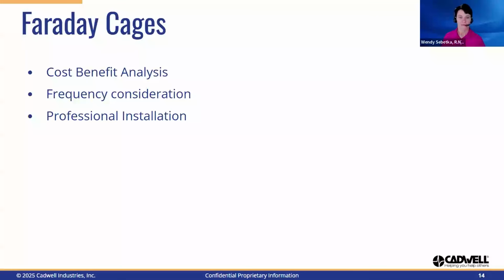The question of installing a Faraday cage always comes up when talking about preventing noise. If considering installing a Faraday cage, you will want to perform a cost-benefit analysis to ensure the expense is worth the benefit. You will want to ensure the proper cage is selected, taking into consideration the frequencies you need to block, as high frequencies require a smaller hole size, while lower frequencies would require a larger hole size. Installing the incorrect option could lead to no improvement or even worsening of your noise.